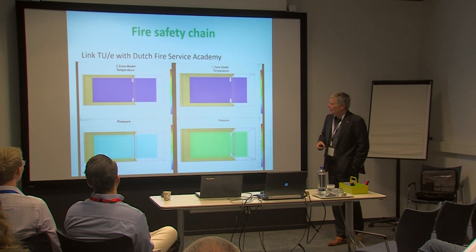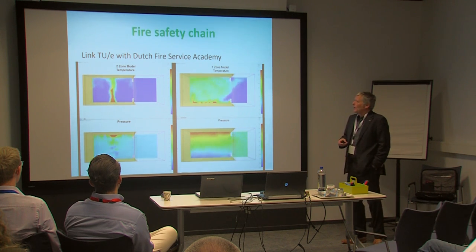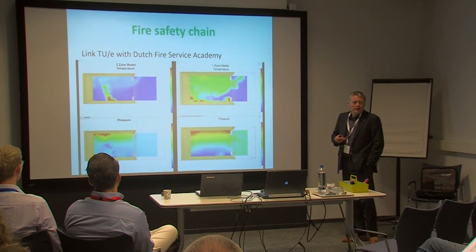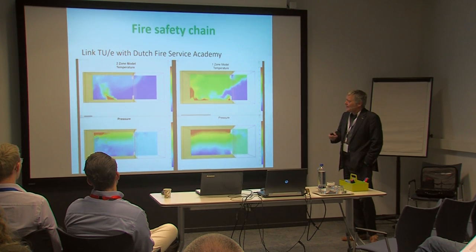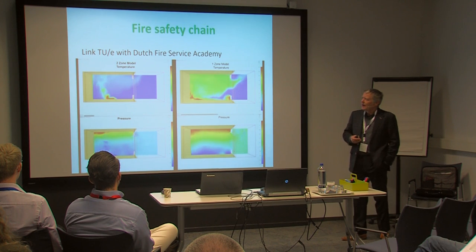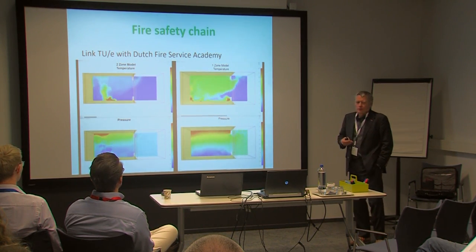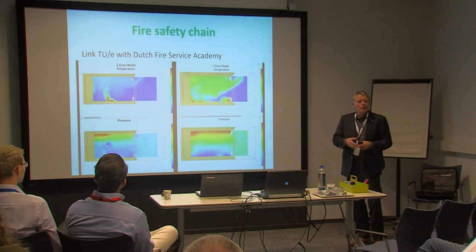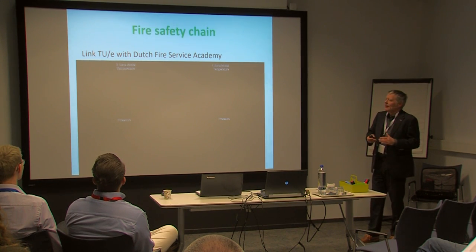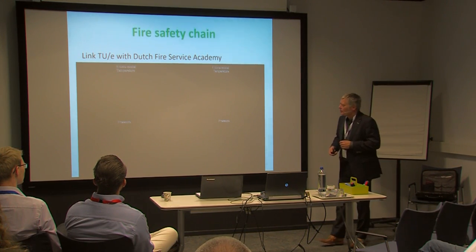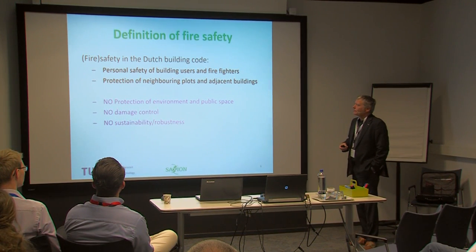We do CFD simulations with localized fire on the left side and fully developed fire on the right side, showing air exchange between inside and outside. This is a simple example, but it makes sense because in experiments we sometimes encounter under-ventilated fires — localized fires that are already ventilation-controlled. When a fire develops very rapidly, only gases flow out of the compartment and that prevents oxygen from coming in, giving you the risk of an under-ventilated fire.